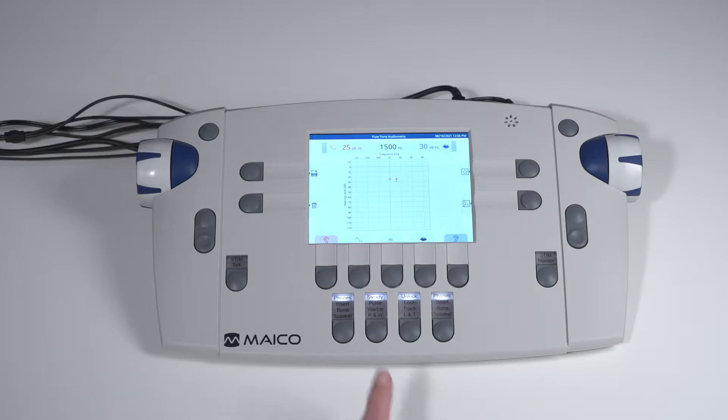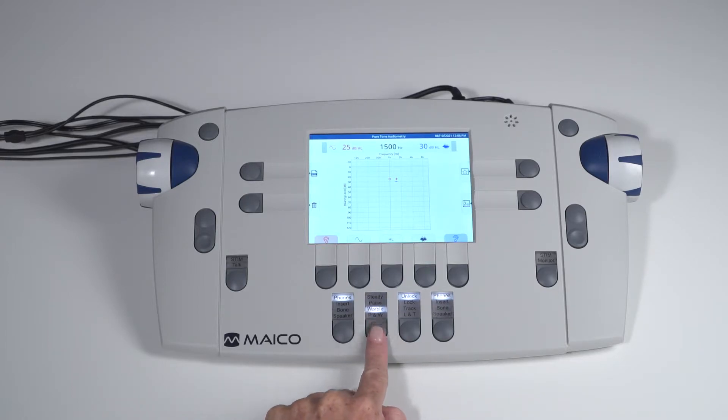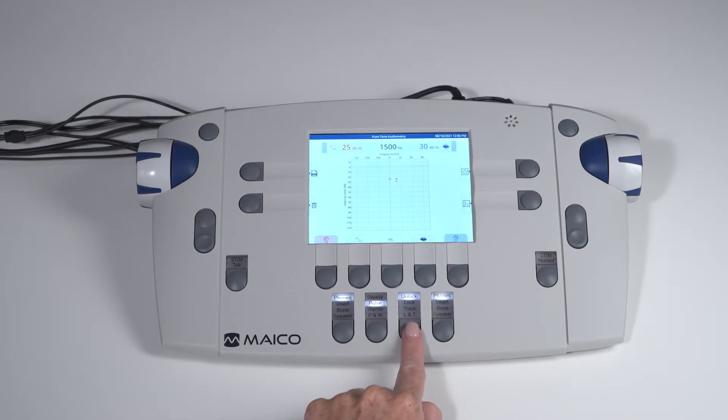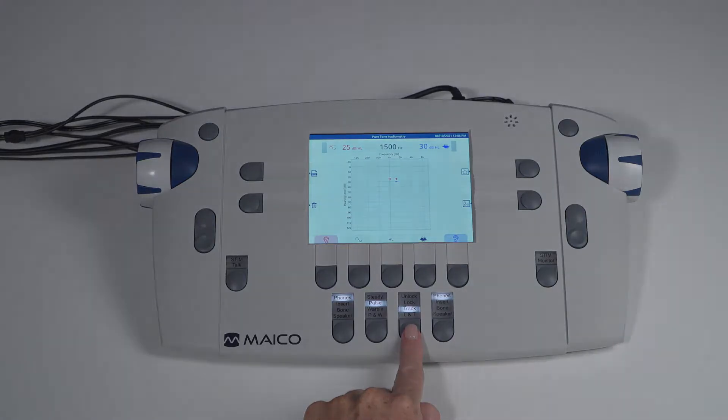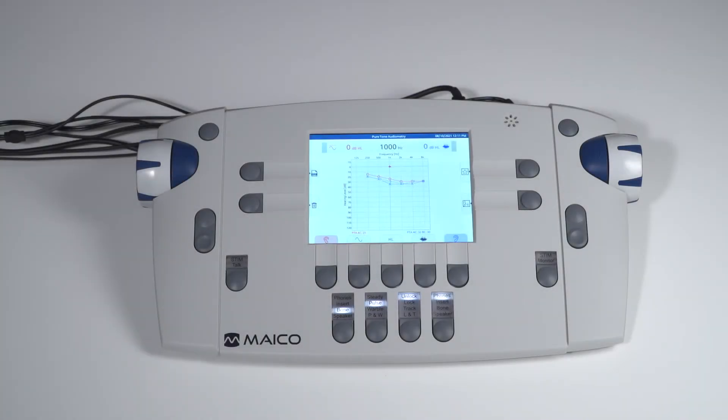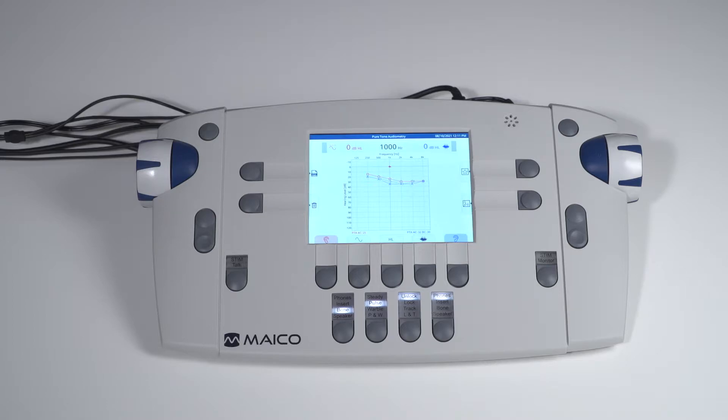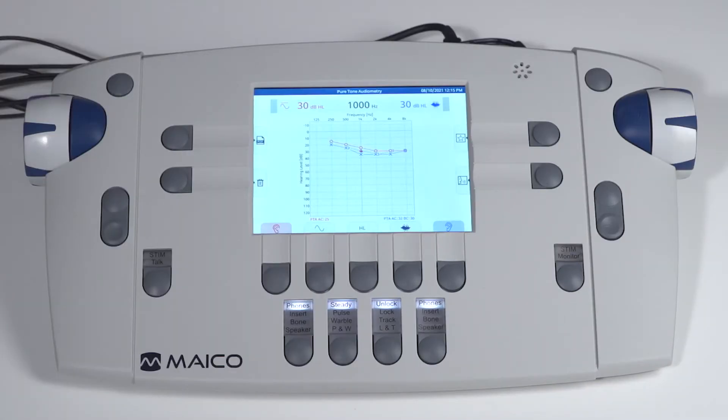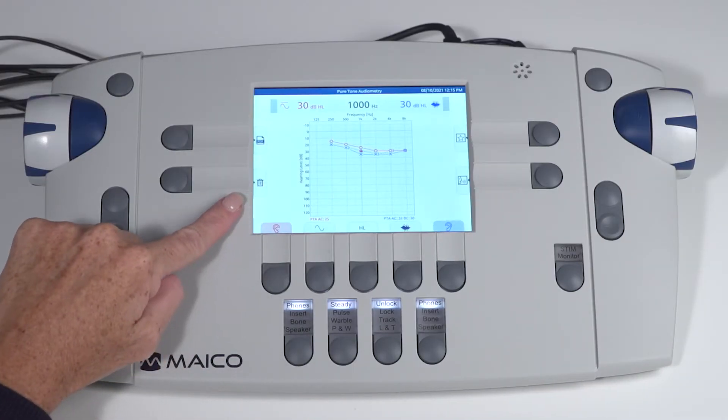Change the tone to pulse or warble with the selection key. Next to that, you can select to lock the stimuli of the two channels or track the channel levels together. Keys around the display change function depending on the screen you are in. These keys have two operation modes, a quick select and an advanced select. With quick select, the icon shown next to the key indicates what action will be taken. When a closed arrow is shown on the key display, this indicates advanced selection is also available for that key.